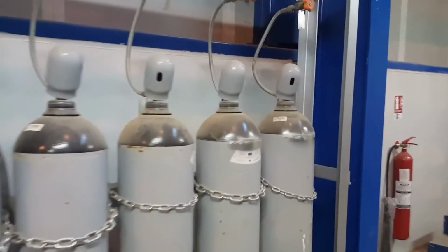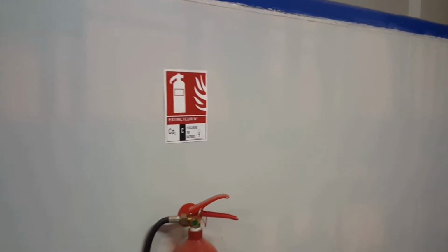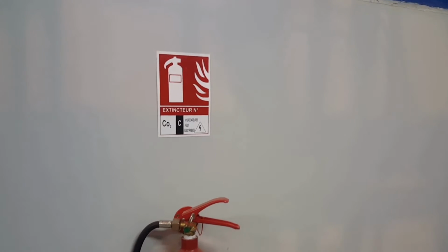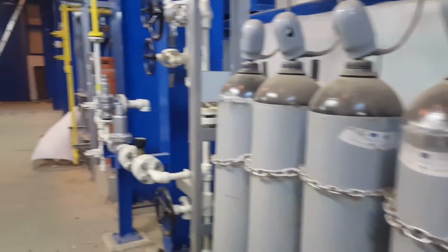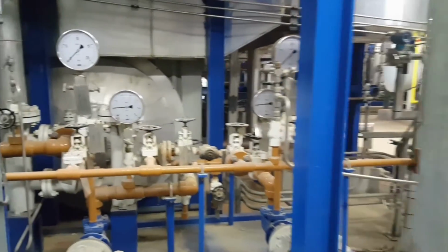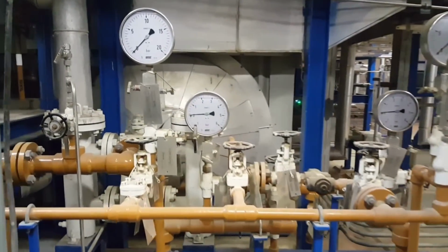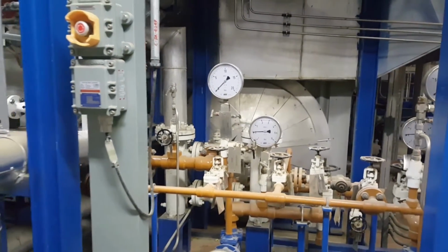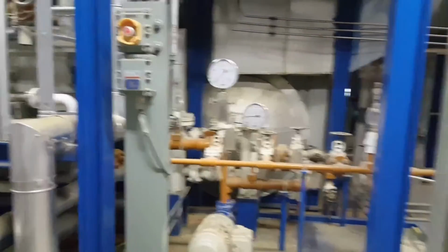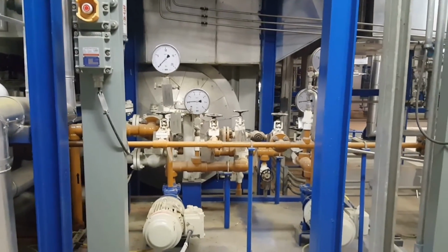The demand for steam from a boiler is called boiler load or steam load. When boiler load increases, more fuel must be burned to produce more steam. When boiler load decreases, less fuel must be burned. Changes in boiler load also require changes in the airflow to the boiler. The mixture of fuel and air supplied to a boiler is called the fuel-to-air ratio. It's important to maintain the proper fuel-to-air ratio to avoid combustion problems.